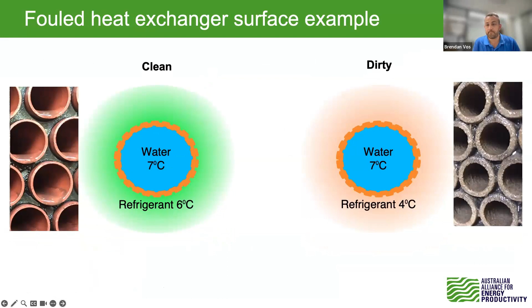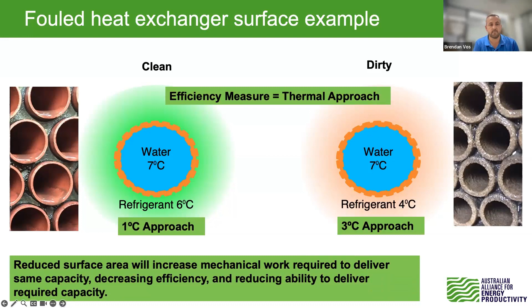So what we're doing here, as a summary, is we've reduced the surface area and we've increased the amount of mechanical work that the chiller has to do. Why this is important is you can also impact the capacity that you can deliver, because we're just not getting that heat transfer, and it often goes unnoticed. So I really wanted to do this slide. This was my favorite one.